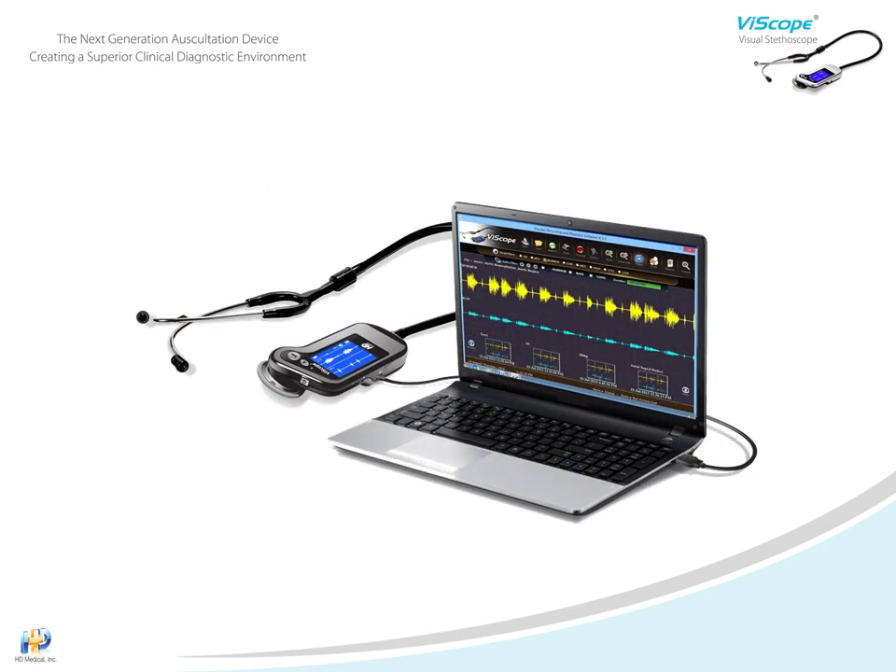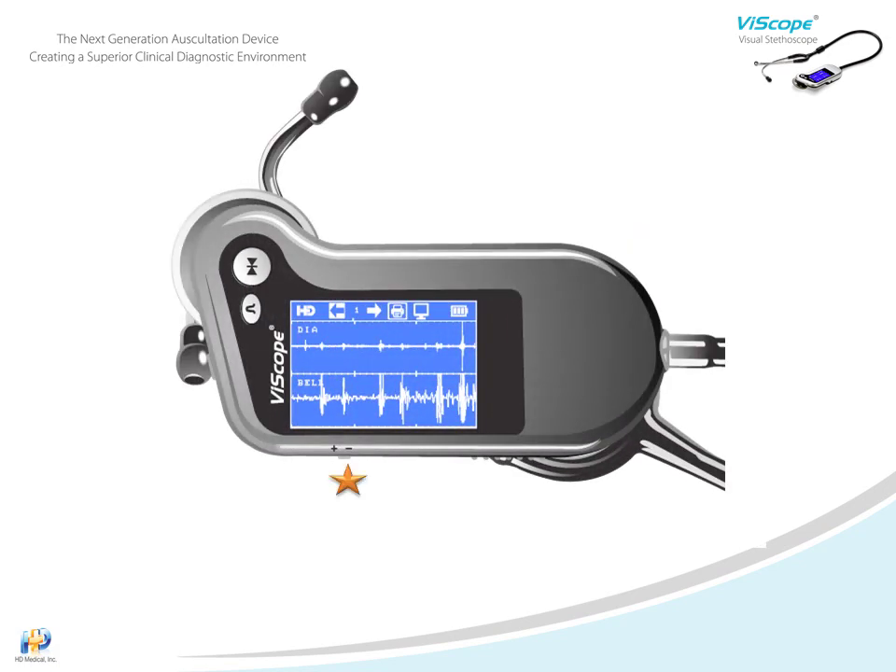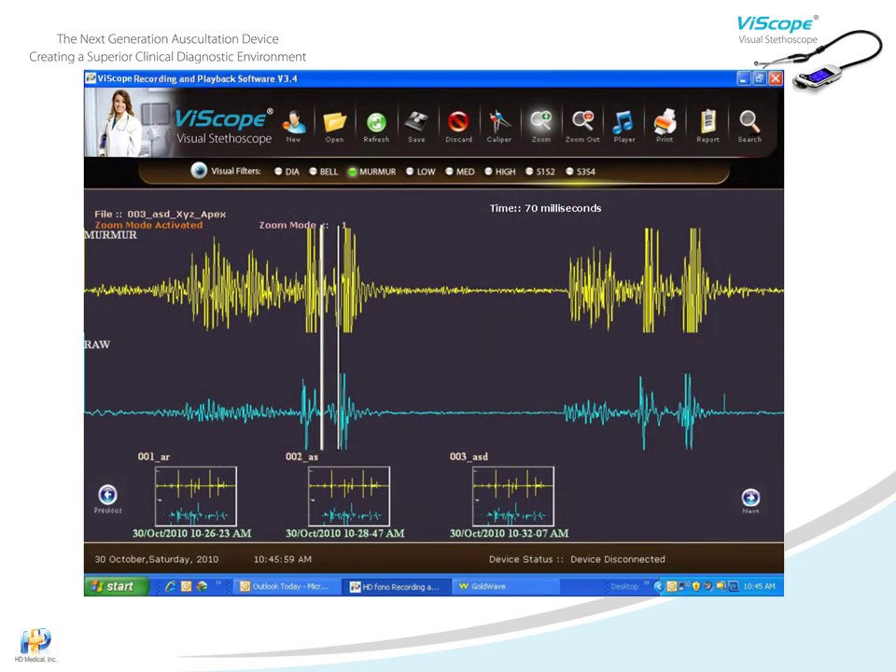To save the acquired data for patient records or further studies, we will need to transfer it to a computer. Continuing to use the three-way key, scroll to the transfer icon and press the key to transfer the saved heart sound waveforms. After being transferred, they are automatically erased from the ViScope. Beyond patient record retention, there are multiple tools in the ViScope software, including caliper and zoom functions, which we will cover in another educational presentation.